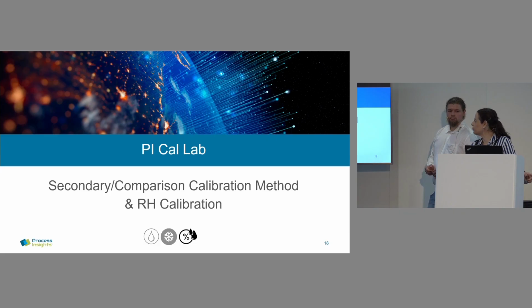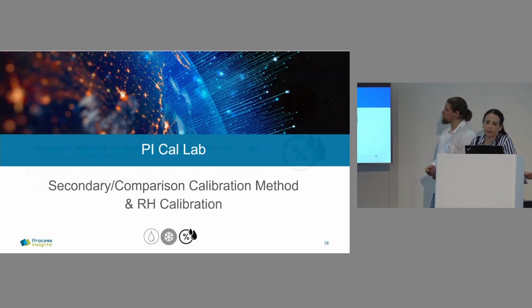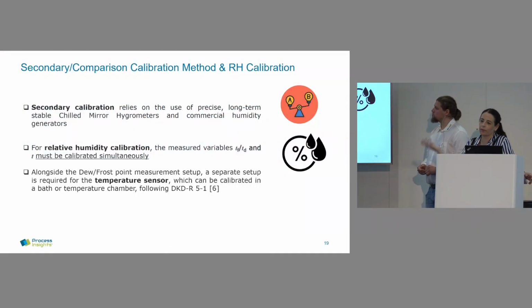Very briefly, on our secondary comparison method, I think it's very easy to understand that we have one reference instrument and a second one, then we compare the results. Of course, we don't need the primary generators, we can use commercial ones. And when we are calibrating relative humidity, we are calibrating at the same time the temperature sensor inside either a chamber or a bath, depending on the type of calibration.